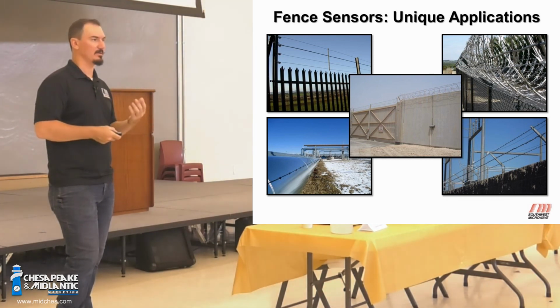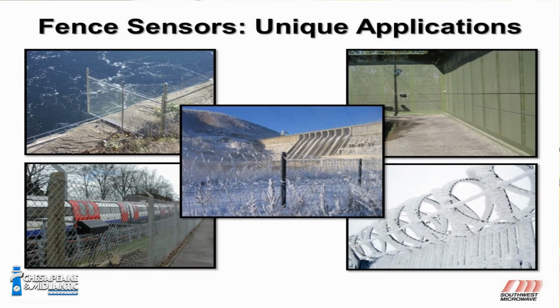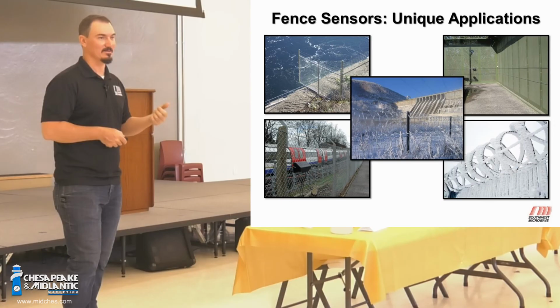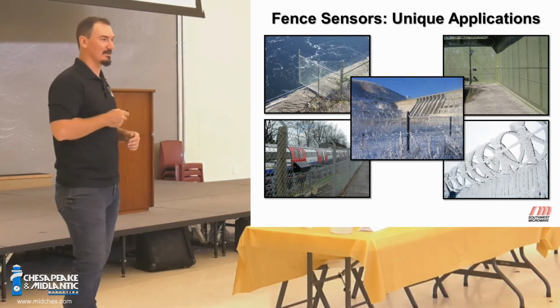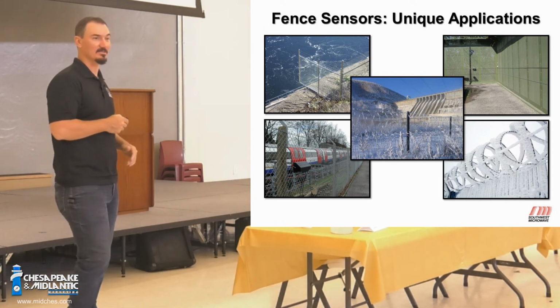And so the armored cable is our standard sensor cable with an armor wrapped around that and then a second outer jacket. And the idea there is that it can be installed on those different materials and can be cut, but it's still weather resistant and weatherproof. It's still pretty easy to cut through those cables, armored or not. But you can cut the outer jacket with the razor coil, barbed wire, anything like that, and it won't affect sensor performance.